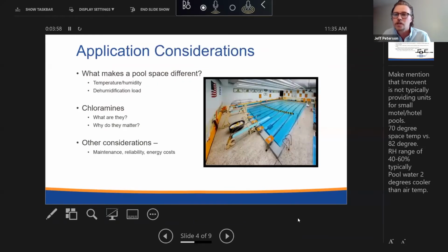So application considerations. What are some things to keep in mind? The name of the game with a pool project is you've got this large body of warm water in an indoor environment, so you need to dehumidify that space year round. Unlike an office space, where your space temperature is going to be in that 70 to 75 degree range and 30 to 50% relative humidity year round, for a pool your space temperature is usually in the 82 to 84 degree range, right? So the space is at a much higher dry bulb temp. The relative humidity range is 40 to 60%.